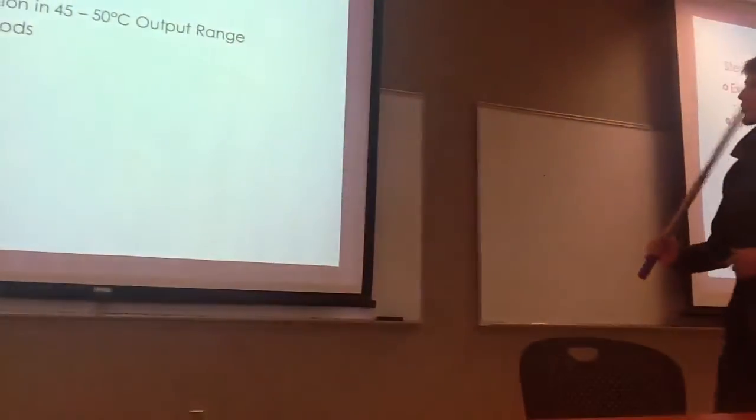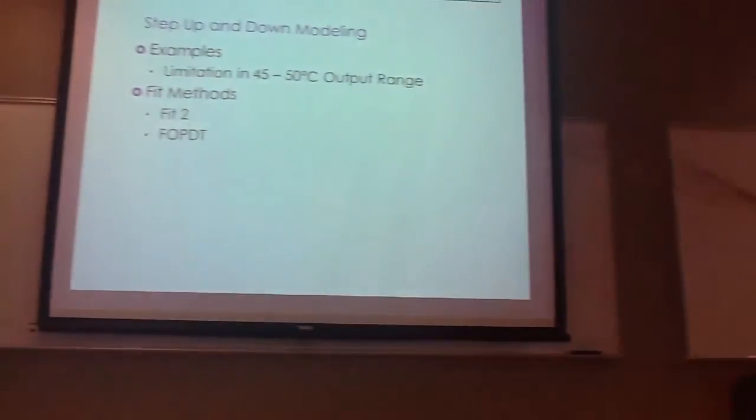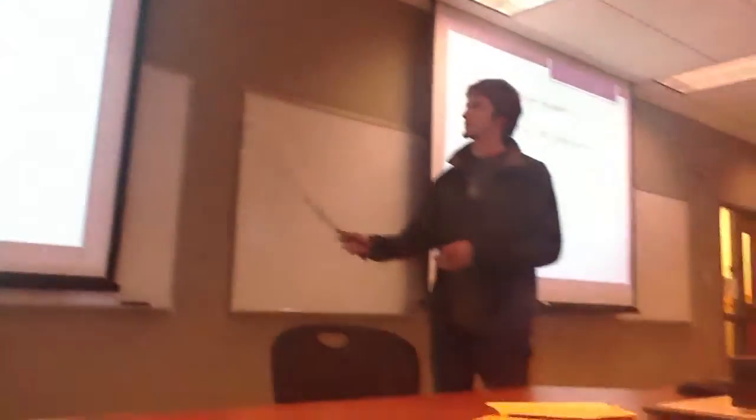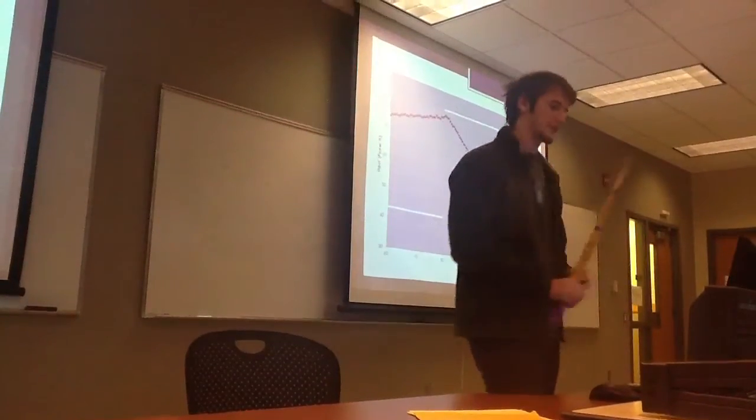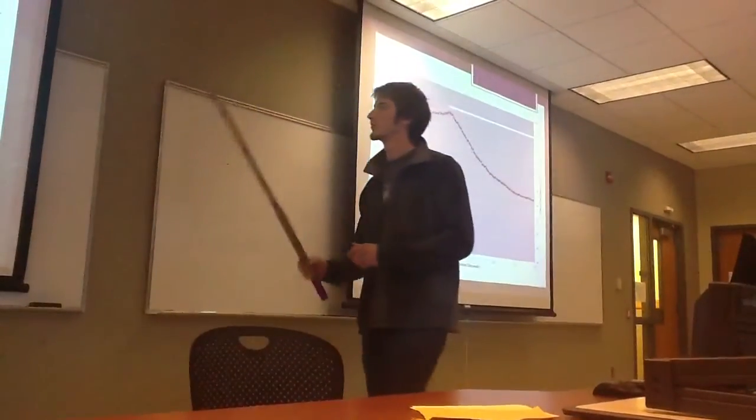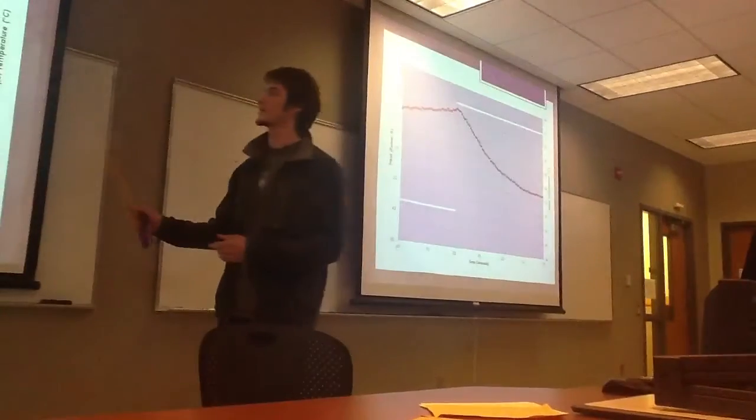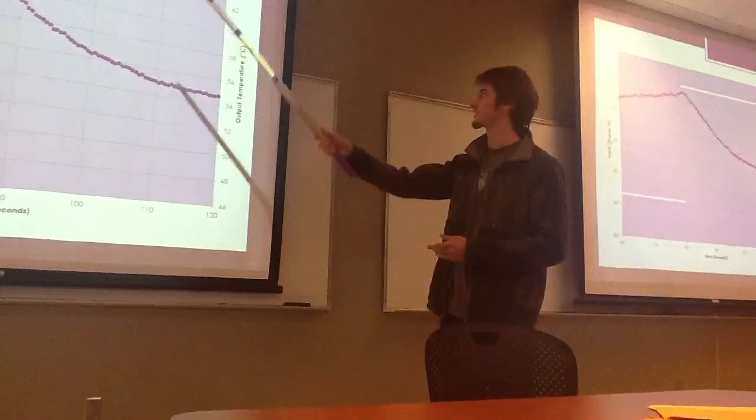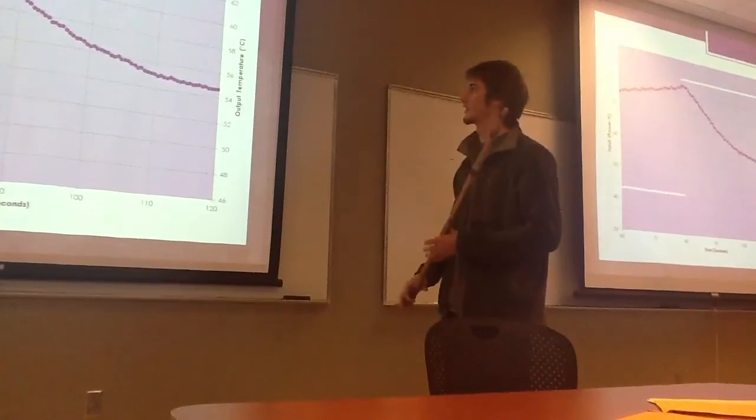Then we moved on to step up and step down modeling, and I'm going to go over the examples and show you the limitations of the 45 to 50, and then the two fit methods we used. Here's an example of a step up, and as you can see it's temperature, and we're cooling it, so when our step up goes it's actually cooling it, so we have a negative gain on our step up diagram.